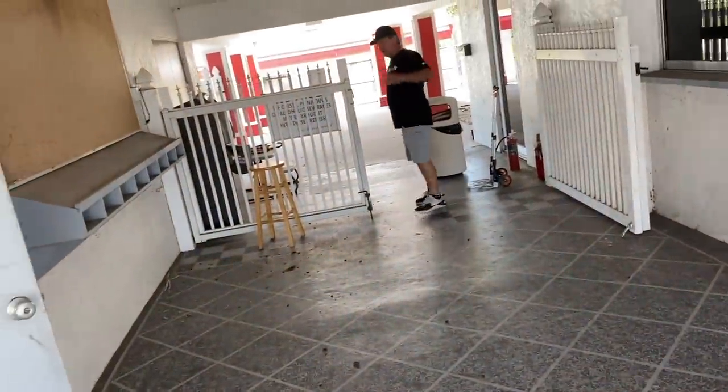All right, boys, we got a lot of stuff online. We got to certainly figure out a few things with the bathrooms. We're going to have to figure out the valves in there because a lot of the valves are just pretty much cooked on the urinals and some of the toilets. So what do we got to replace? Is it the cartridge on those? It's a whole diaphragm set. So we're going to have to put some diaphragms in those, but we'll obviously have a video coming on that eventually. We at least got the water system online today, which is a huge step.